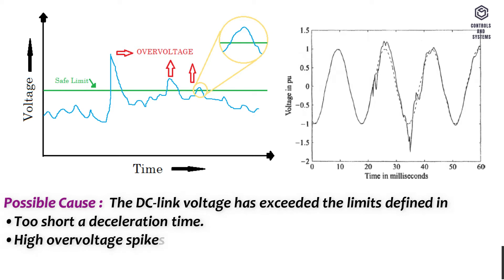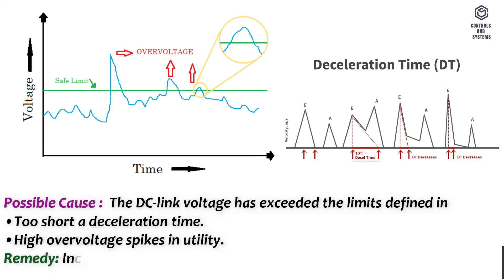Fault code 2 – Overvoltage. Possible cause: the DC link voltage has exceeded the defined limits due to too short a deceleration time or high overvoltage spikes in the utility supply. Remedy: increase the deceleration time.